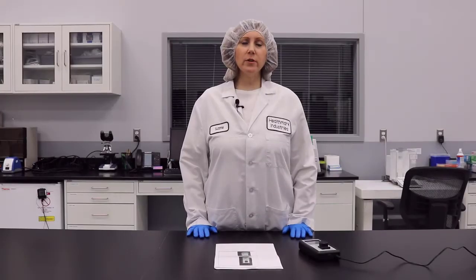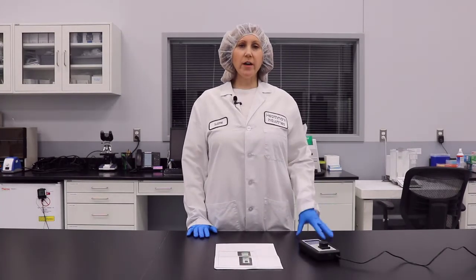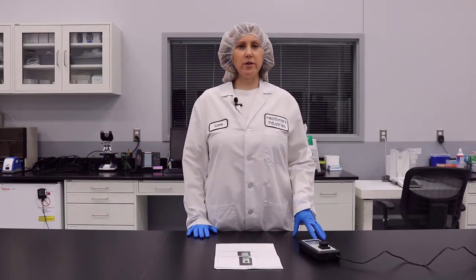At 10 minutes, the fluorometer will take a reading. The value displayed before 10 minutes is disregarded. Please note that the timer on the fluorometer will keep running, but the reading displayed is taken exactly at the 10-minute mark. Now that you have your reading, you can go back to the IFU and read the interpretation of results and the contraindication of test results.